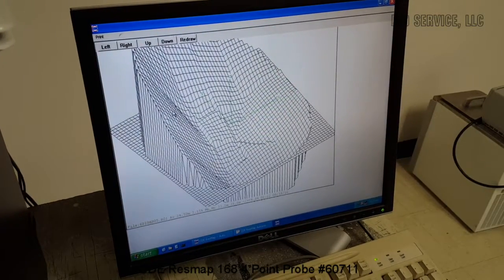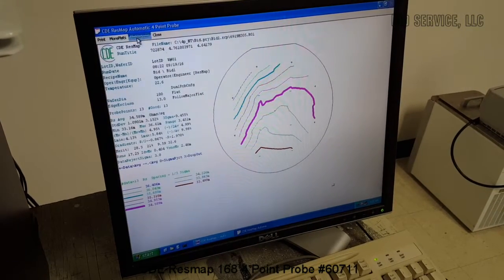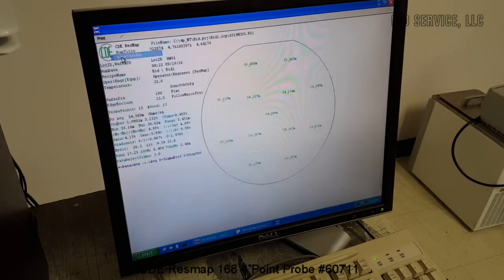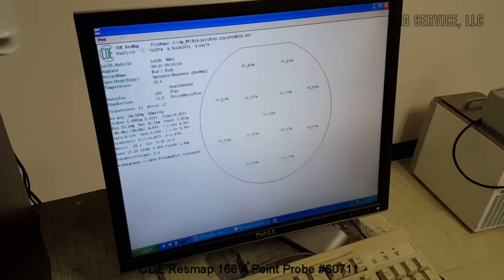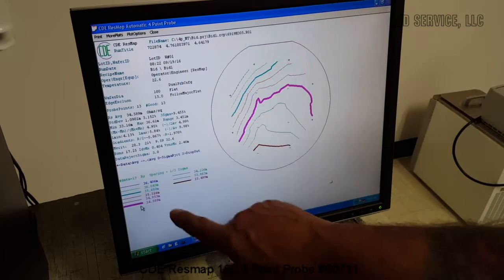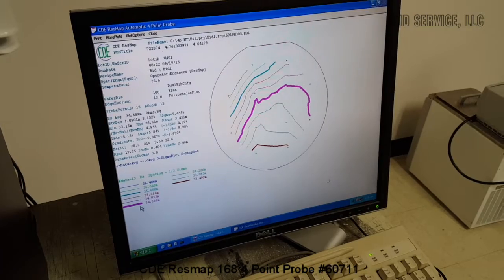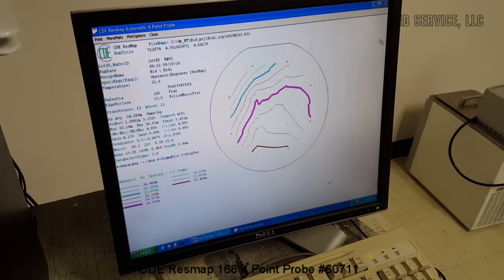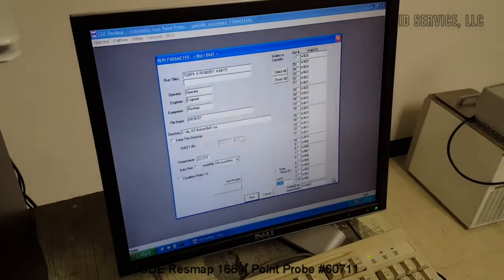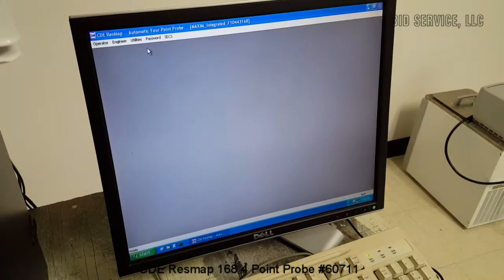This can be rotated, so it's pretty powerful software. There's different plot options that come up, different other plots. You can do a wafer data plot, which shows you what you originally had. And shows you your readings down here, standard deviation, a bunch of information that you need. I'm going to close this window.